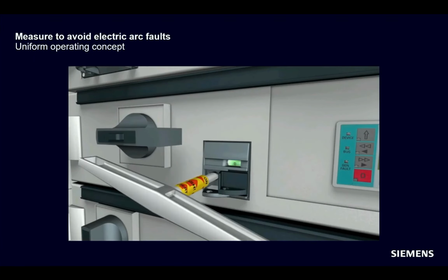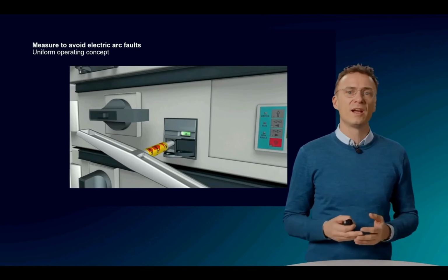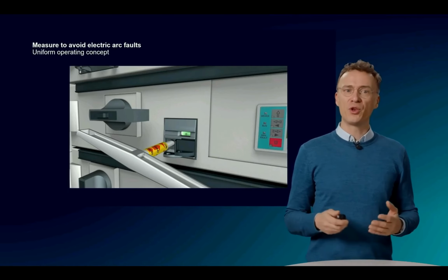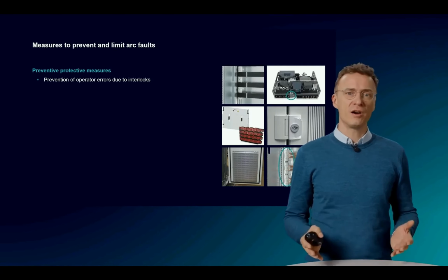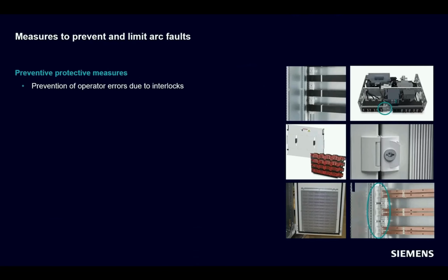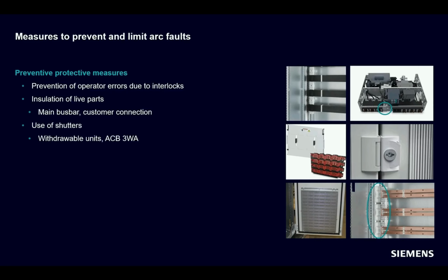Passive measures here would include a uniform operating concept for all withdrawable unit sizes, various locking devices for main switching devices, and mechanical locks that allow switching only when the withdrawable unit is correctly inserted and when the door is closed. Other measures are the insulation of the main busbar and the customer connection, the right selection of internal separation, the use of shutters at the distribution busbars or adapter plates or on the circuit breaker. These can prevent live parts from being accidentally touched with a tool during maintenance work. Further ones include, for example, the use of coding. This avoids confusion between withdrawable units of different ratings and circuit breakers of different ratings.